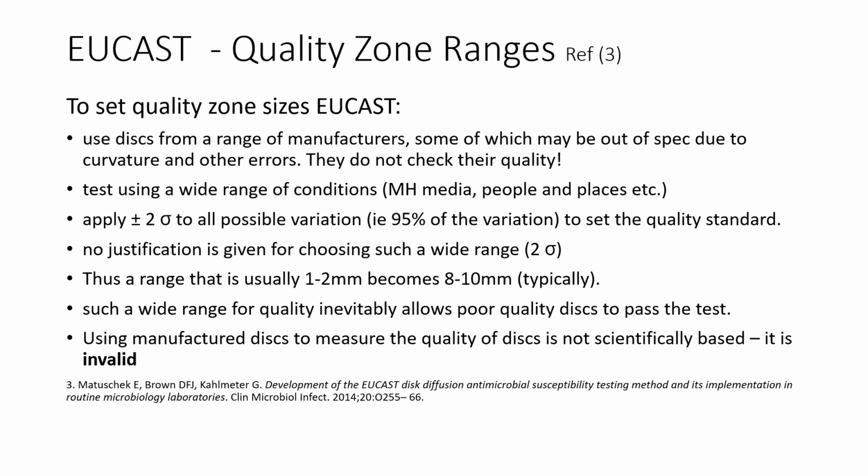End users don't use an assay to test the quality of the discs. They use quality zone ranges that are published by various bodies, including EUCAST. So it'd be useful to know where these quality zone ranges come from.